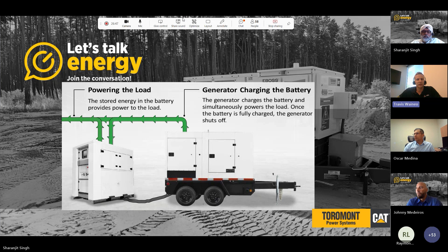It works pretty well, but there are some transitional concerns where you're switching the loads between the battery and the generator. So this is what I call a DC coupled system - something we put together, that front system. Because it's DC coupled, the generator turns into a battery charger, and the battery is what powers the load directly. There's never a transition between the generator turning on and off and the AC output signal having to transition between the two.